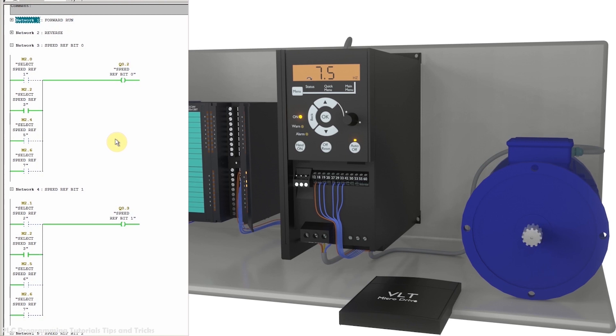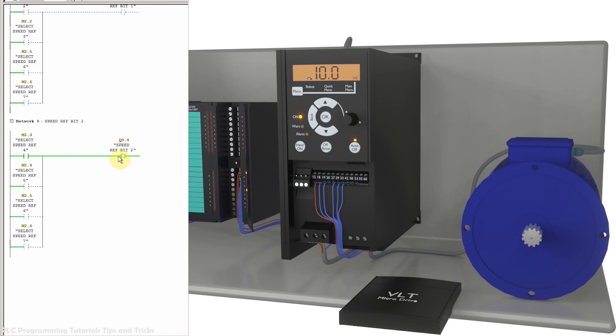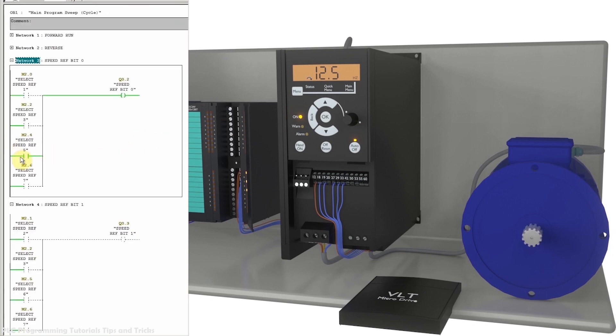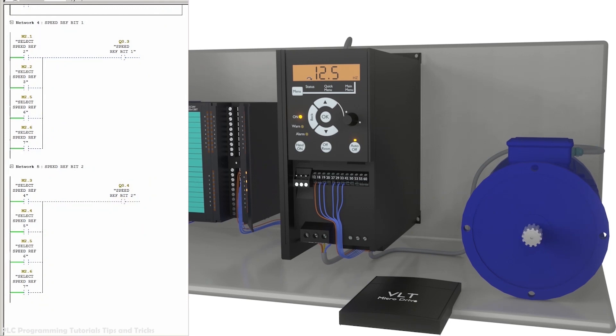The motor starts running at 7.5 Hz. Next, turning on M2.3 (select speed reference 4) turns on Q0.4 (speed reference bit 2) and the VFD loads preset frequency reference 4 — 10 Hz. The motor starts running at 10 Hz. Turning on M2.4 loads the fifth preset frequency reference and the motor runs at 12.5 Hz.